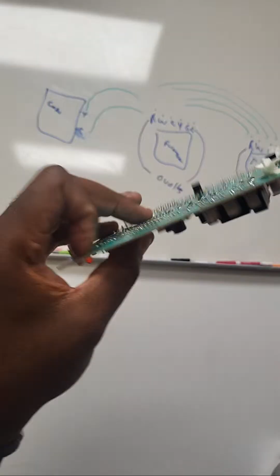Now guys, you got to understand what this means. Basically, R and C are the 2 wires coming off your transformer. So I had to step back and figure out cause and effect. My effect is I don't have 24 volts from R and C. What can cause that is my transformer, which is a part that's not on the circuit board. But the purpose of the transformer, let me write this on the board and sum it up simply: you got your 115 volt hot, neutral, and then you got your primary and secondary, so R and C.